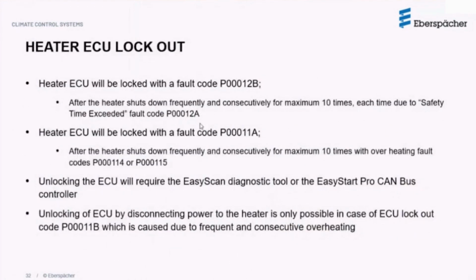As far as ECU lockouts, yes, it's possible. Your ECU will lock out if there are more than 10 consecutive failures to start by the heater. Each time the heater fails, just like on the electronic, the heater will make up to 2 start attempts before it fails. And if it does fail after making 2 start attempts, the code P00012A will appear. Once this happens more than 10 times, the ECU locks out, and the lockout code would be P00012B. Same is the case with overheating events—any overheating event that produces codes P00114 or P00115, after 10 such events, the ECU will lock out with the code P00011A.